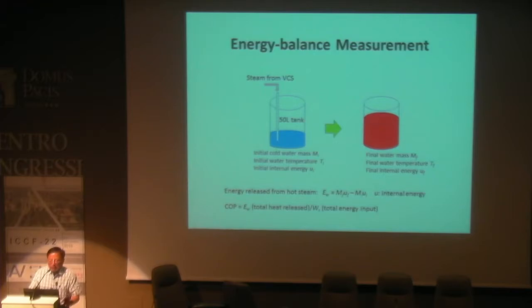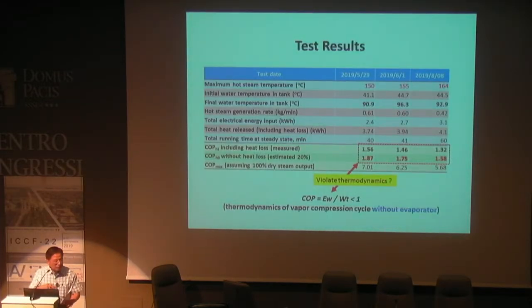So I met this company several months ago, and we have a cooperation. We try to measure what the COP is. The company didn't care about the COP before, but I was so curious about it, so I said, I'm going to measure it and see what happens. And then I did a very simple experiment just by energy balance. The output steam is just put into cold water, and I do an energy balance calculation. And it shows the COP is over 1.5 to 1.3, depending on steam temperature.